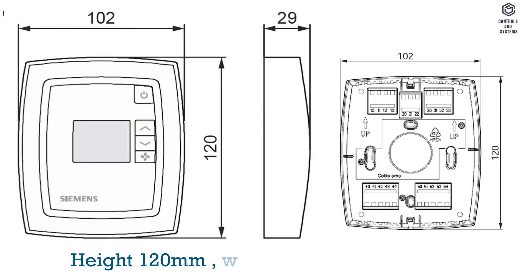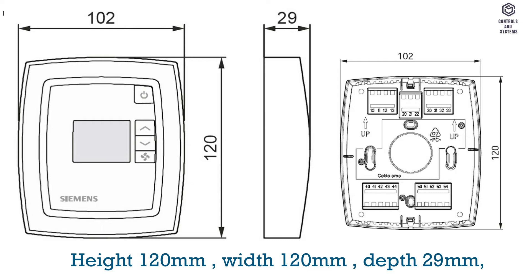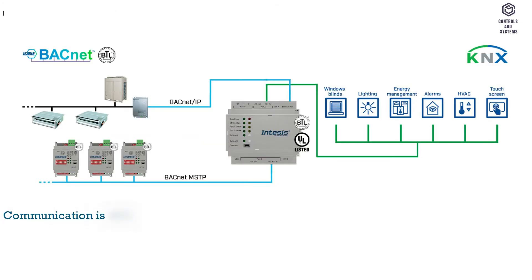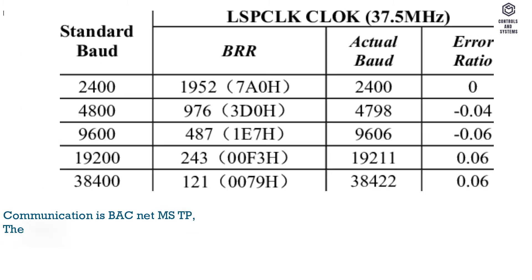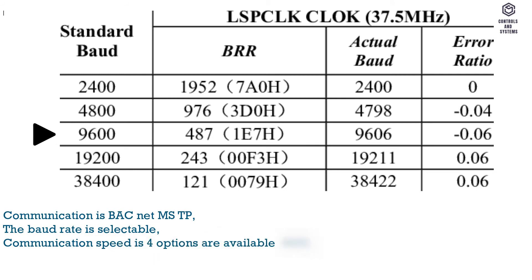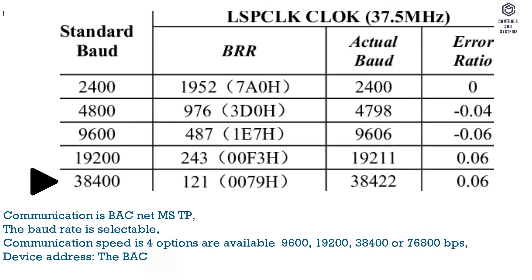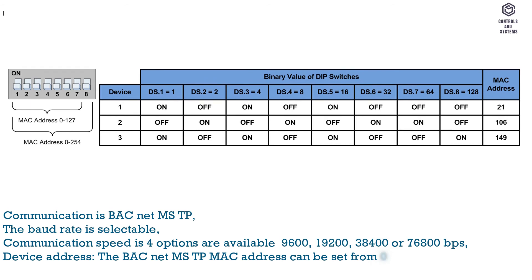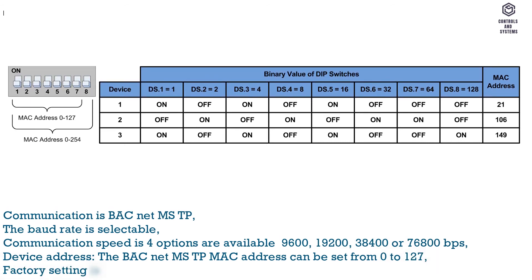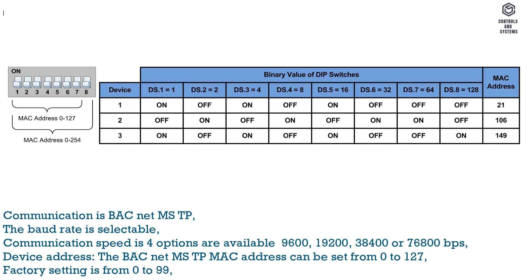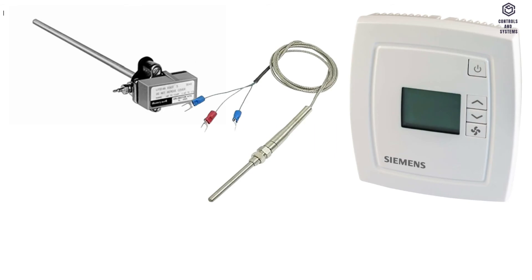Dimensions: height 120 mm, width 102 mm, depth 29 mm. Communication: BACnet MS/TP. The baud rate is selectable — four communication speed options are available for the RDB 160BN: 9600, 19200, 38400, or 76800 bits per second. Device address: the BACnet MS/TP MAC address can be set from 0 to 127; factory setting is 0 to 99.